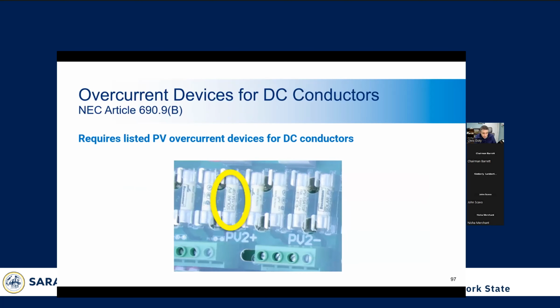As I think I mentioned earlier, PV systems have to use PV rated fuses. So you want to make sure that the fuses, in this case, this was done correctly, but you want to make sure that the fuses are rated for PV and obviously DC rated.